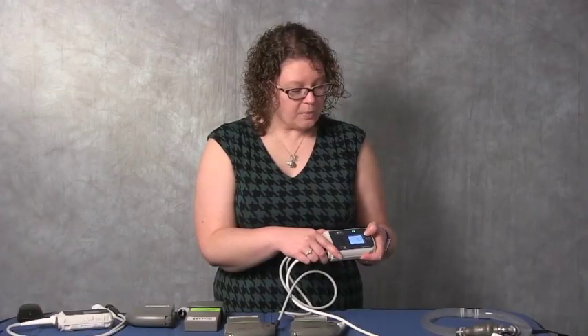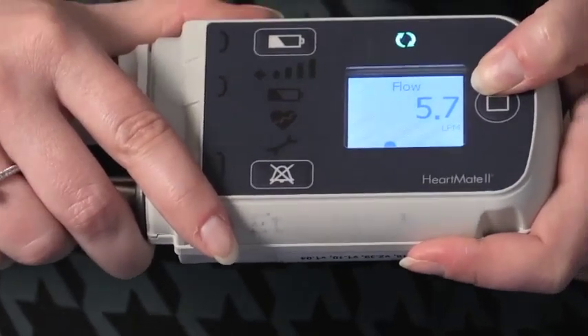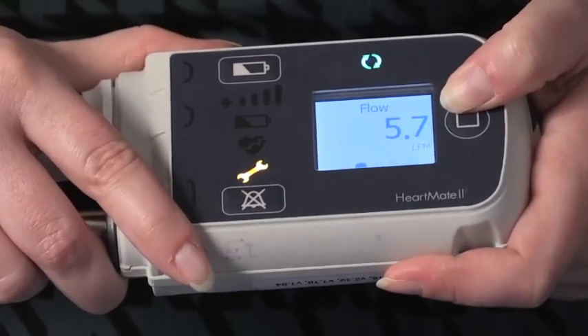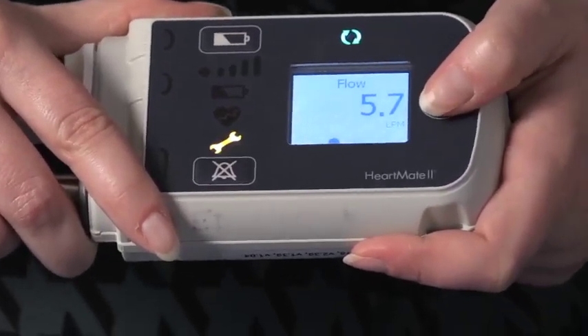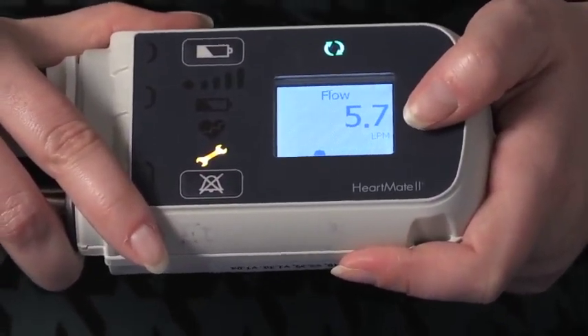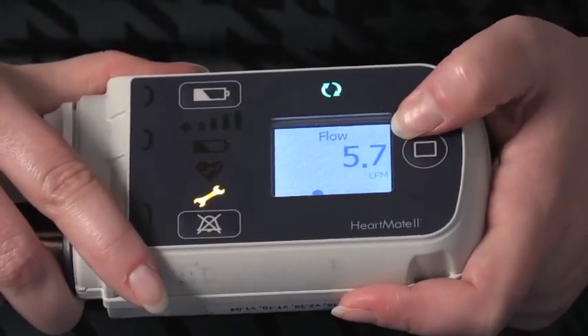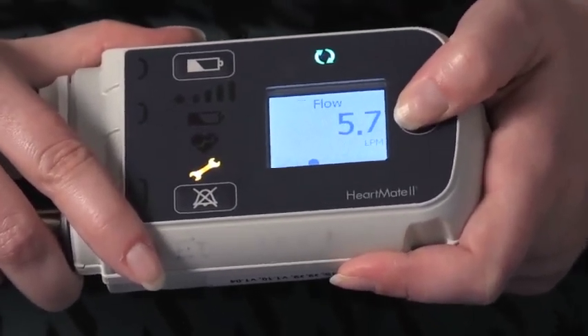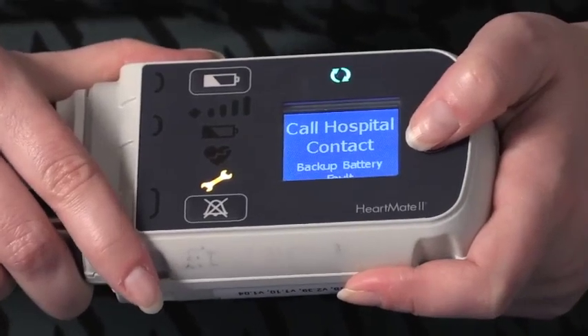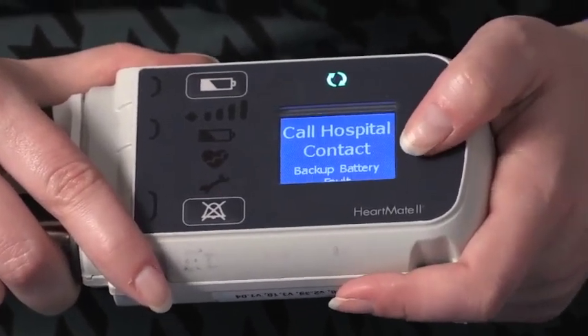The second number that comes up is the flow. It's important to know that there is not a flow probe inside this pump, but we are approximating how much blood in liters per minute is going through that pump. As you can see right now, 5.7 liters per minute. I like for it to be above 3. The low flow alarm goes off at 2.5.